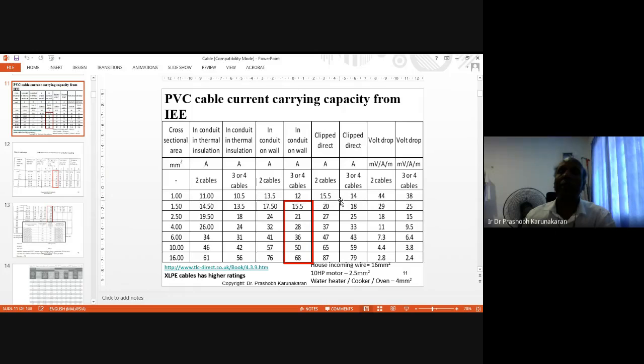So clip direct was 14 amps, but now in conduit with thermal insulation it can only carry 10. What does this mean? The more you cover your wire, the less current it can carry - your carrying capacity is reduced when you cover the wire more. So where is the most covered wire you can find? Underground cable. Let me show you underground cable.